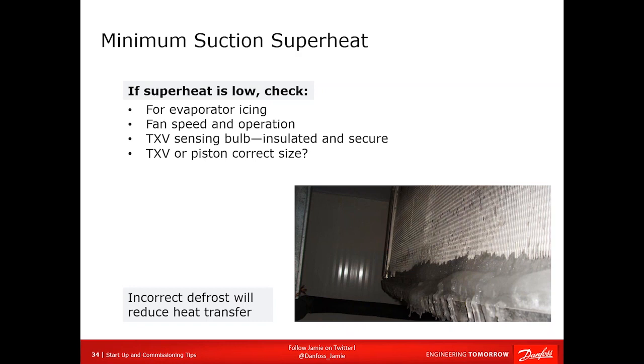Fan speed and operation. Is your fan run at the right speed? Is your fan running right? Did somebody put the fan blade on backwards? Don't laugh. I saw this on condensers one time. It was amazing. The air is supposed to blow up. It's blowing down. Why? Well, the fan blades are put on backwards. Is the TXV or piston the correct size? Never assume it is.